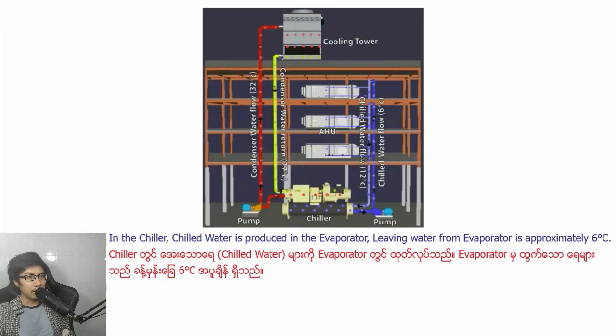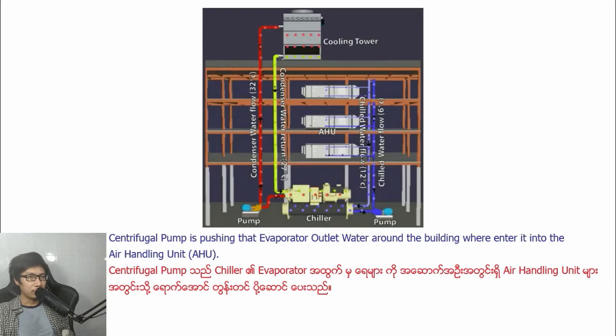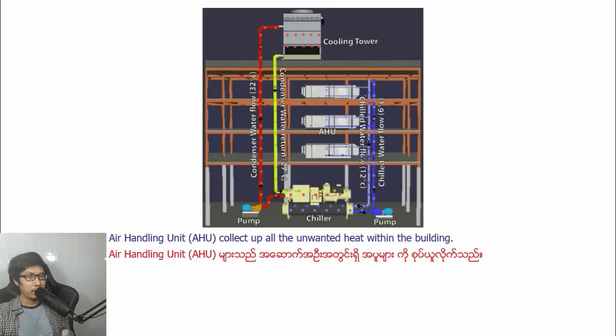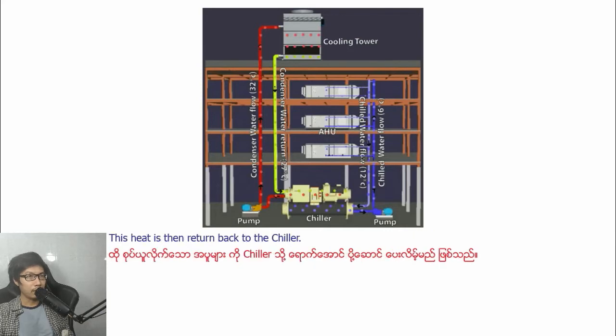In the chiller, chilled water is produced in the evaporator. Leaving water temperature from the evaporator is approximately 6 degrees Celsius. A centrifugal pump is pushing that evaporator outlet water around the circuit and into the air handling unit. The air handling unit cools the air and the water picks up the heat from the building.